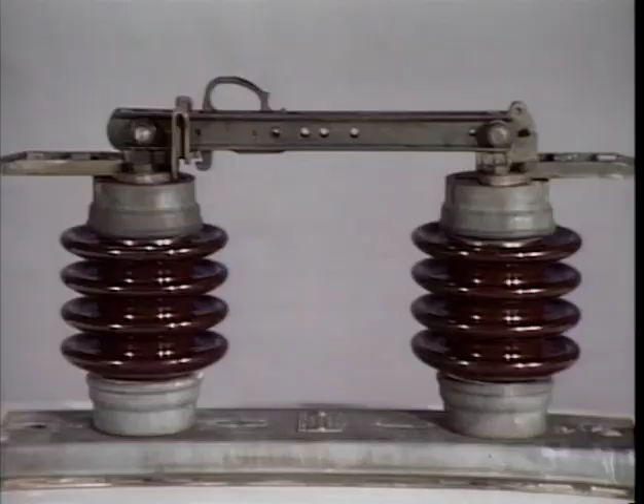Some disconnect switches are designed to be opened under load, but many others cannot be opened until the circuit has been de-energized. You need to have a clear understanding of the differences between the two types of disconnect switches so that you don't make the mistake of opening the wrong switch under load. This could cause sustained arcing and you could be seriously injured. Fortunately, disconnect switches have certain features that let you know whether or not they can be operated under load. We'll look at examples of these two types of switches, and I'll show you what I mean.